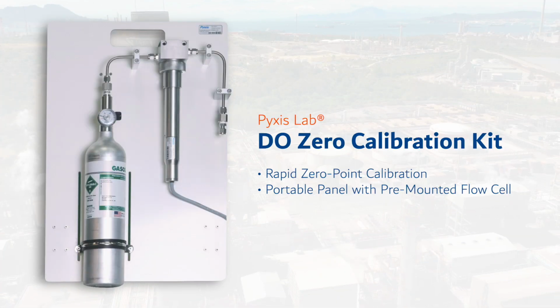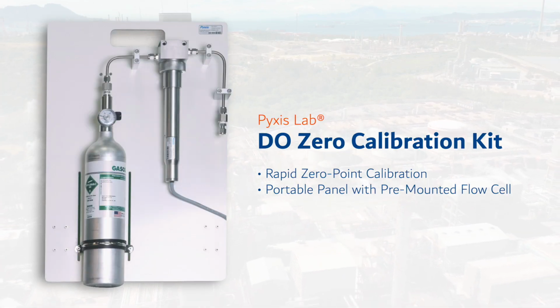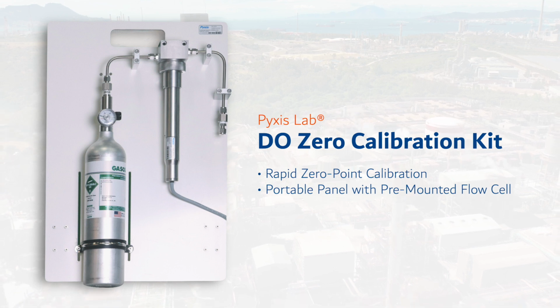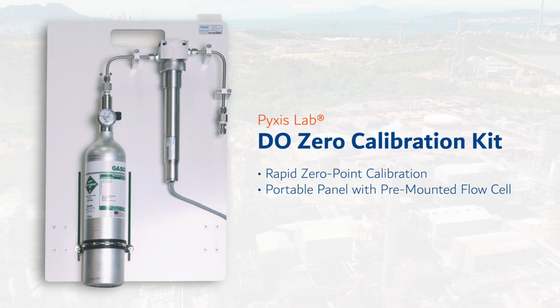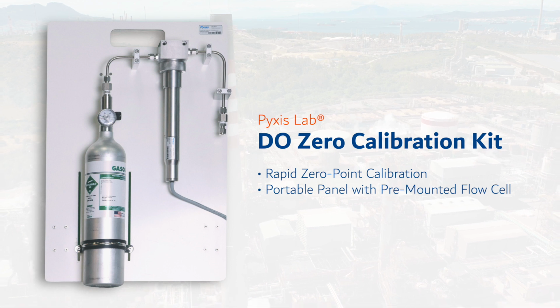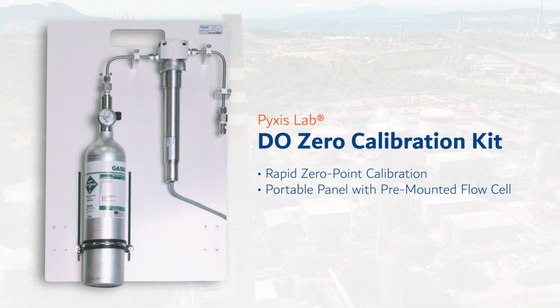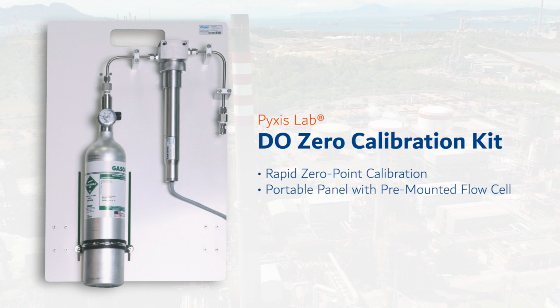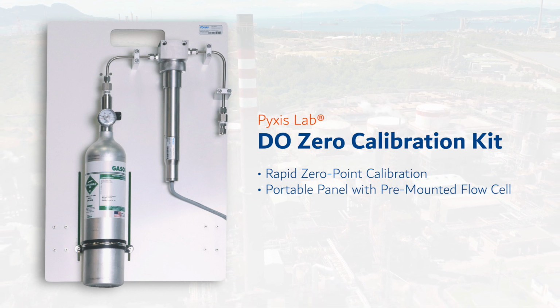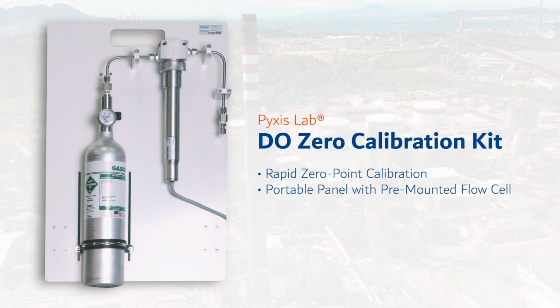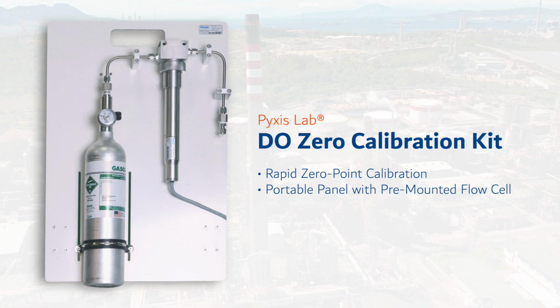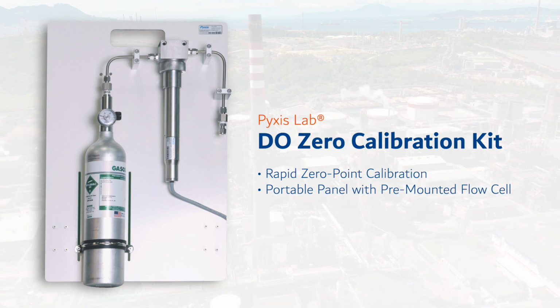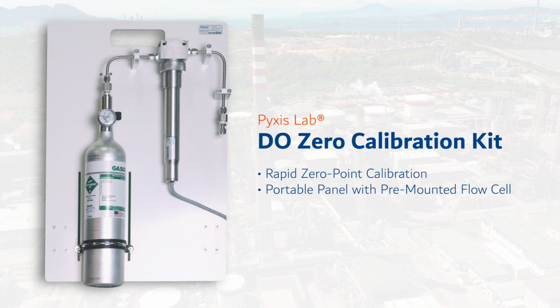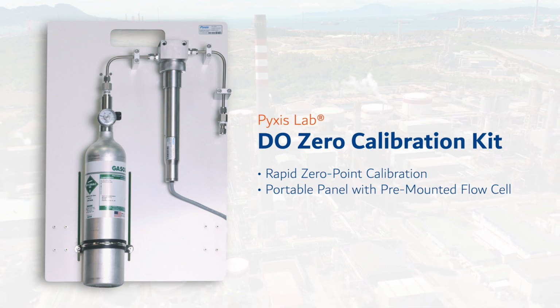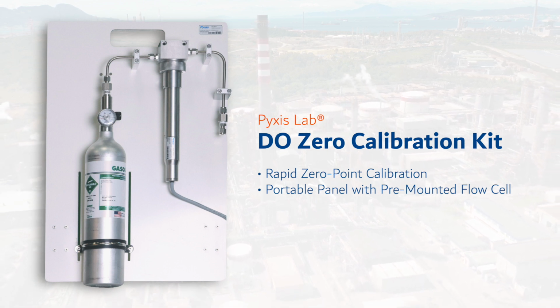For rapid calibration of the ST-774, Pyxis Lab offers the DO Zero Calibration Kit. Sold as an accessory, this kit is a portable panel that comes pre-equipped with the ST-774 flow cell, interconnecting 1/4-inch Swagelok stainless steel tubing, and a calibration gas cylinder shelf. This accessory enables users to remove the ST-774 from service and install it into the Zero Calibration Kit flow cell for rapid zero-point and slope calibration. Once calibrated, the ST-774 may be removed and returned to its normal service flow cell.